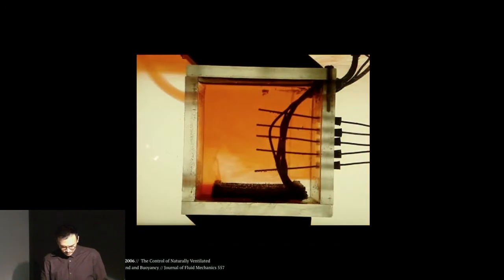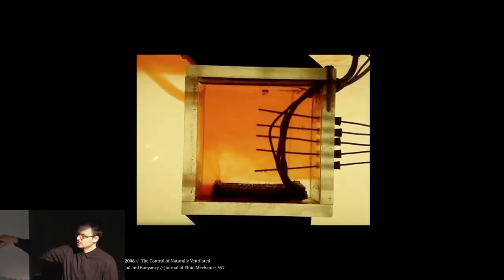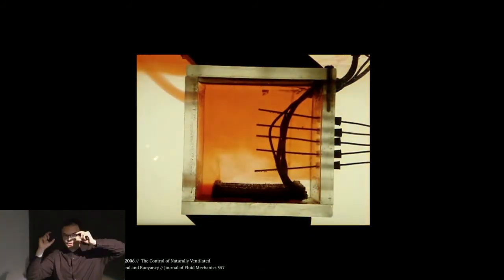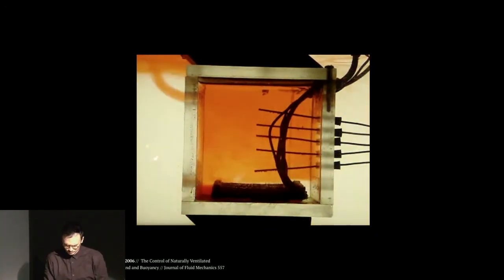That's the basic premise, and the idea is that if you know the height of the building, how much heat load you've got, how much ventilation you need, and what temperature you need to keep out, then you can play with the sizes of the openings or the height of the building until you've reached a sweet spot.